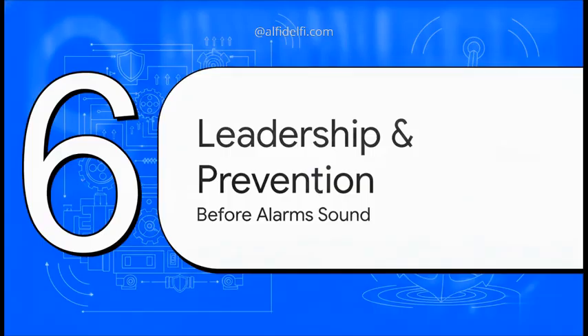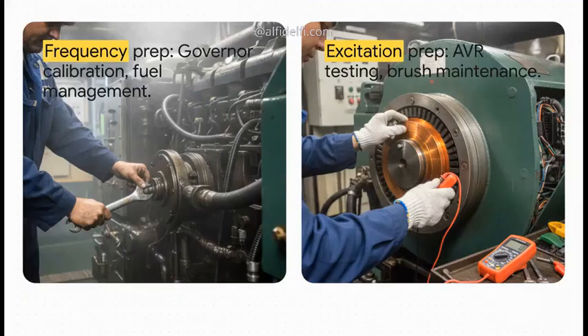Section 6. Leadership and Prevention. A true chief engineer is defined by what happens before those alarms ever sound. To prevent frequency crises, your team has to be absolutely religious about governor calibration, pristine fuel management, and routine vibration analysis of the prime movers. To prevent excitation loss, however, your focus shifts entirely over to the electrical realm.